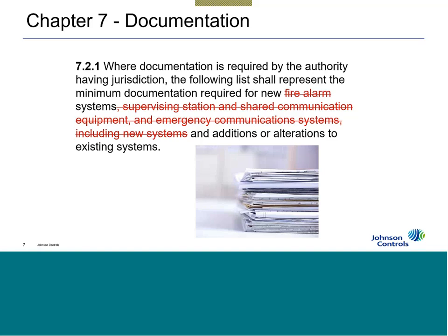So then there were questions about, well, what does Chapter 7 cover? Since 72 does so much, it used to say you needed to use this documentation chapter for new fire alarm supervising stations, shared equipment, emergency communications, and whatnot. And there were some systems where people would come to 72 and say, well, it didn't say it covers my particular thing, so I don't have to use the documentation chapter. And 72 just said, let's just forget it. If it's in 72, you've got to use Chapter 7 for documentation. So new systems, additions or alterations to existing systems, whether it's area of refuge, gas detection, mass notification, whatever it is, you're now under the requirements of Chapter 7 as well. And also, as with all of our codes and standards that we use in the United States, they're minimum requirements. You can do more, but you can't do less.